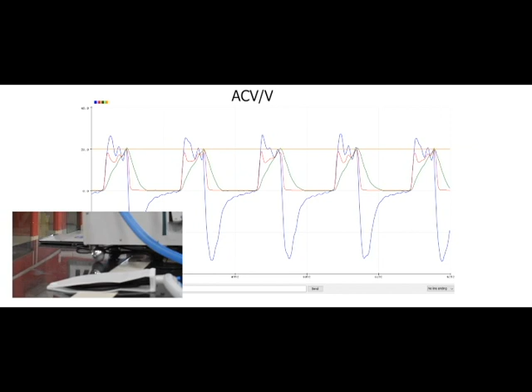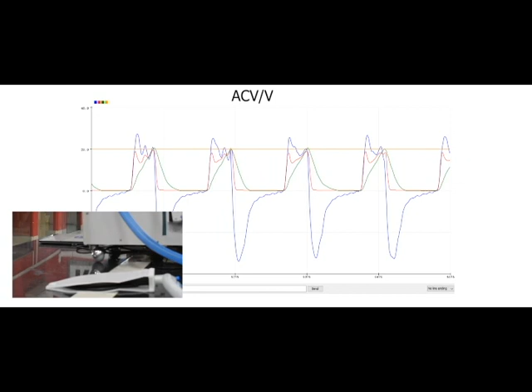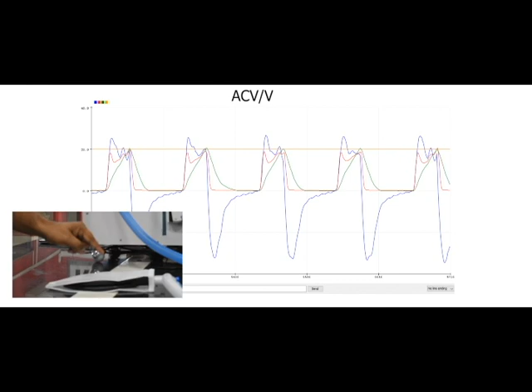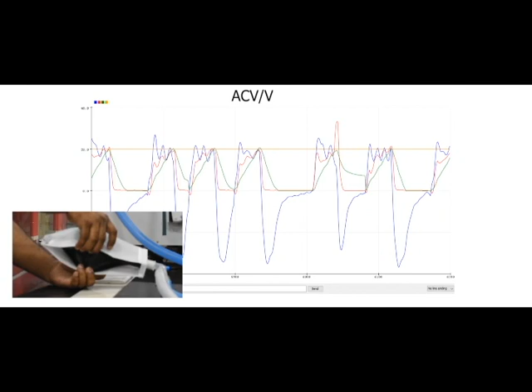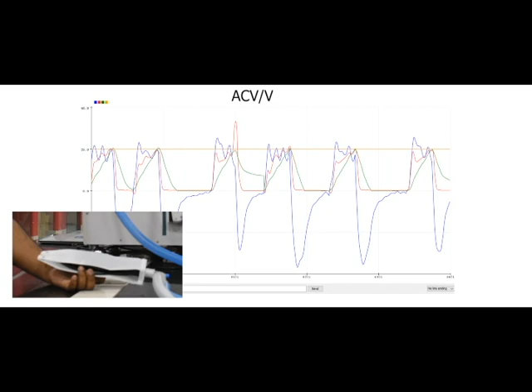Well, now here you can see the ventilator is running in the previously shown CMV-V mode, and it is delivering controlled mandatory breaths, as I have shown you earlier, to reach the given tidal volume. Now, if I do this action for the patient, it will simulate the patient ventilation, and I can show you that this will give an extra breath for the patient supported by the ventilator. So here you can see that we are doing like this, and it is triggering one breath. With the setting of -2, it is triggering the breath, right? So this simulates that if the patient wants to take a breath, our Pranvayu ventilator is supporting the patient's breath, right? You can see it once again. Okay, so the graph is showing that the patient breath is being supported for a target tidal volume.